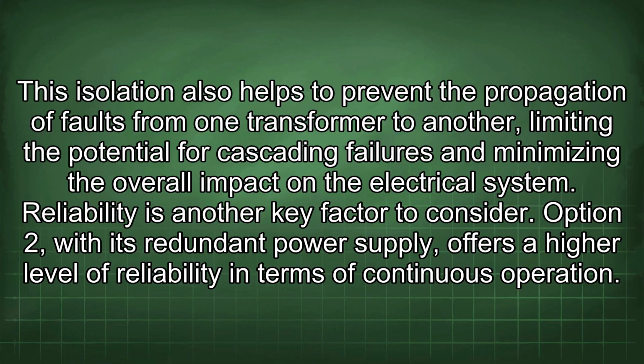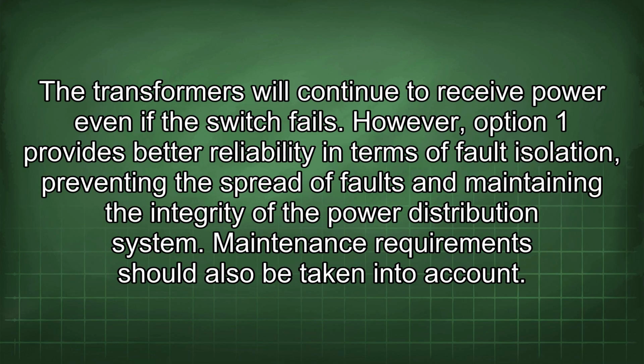Reliability is another key factor to consider. Option 2, with its redundant power supply, offers a higher level of reliability in terms of continuous operation. The transformers will continue to receive power even if the switch fails. However, Option 1 provides better reliability in terms of fault isolation, preventing the spread of faults and maintaining the integrity of the power distribution system.